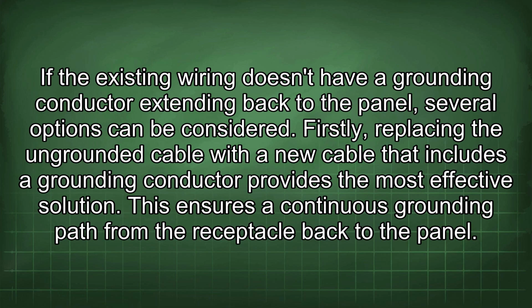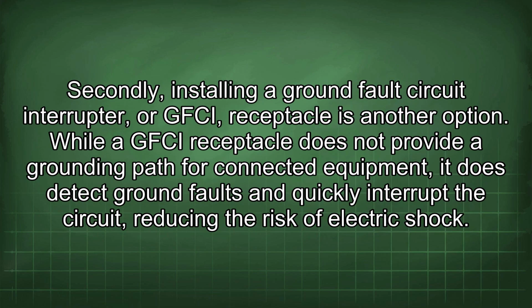Firstly, replacing the ungrounded cable with a new cable that includes a grounding conductor provides the most effective solution. This ensures a continuous grounding path from the receptacle back to the panel. Secondly, installing a ground fault circuit interrupter or GFCI receptacle is another option. While a GFCI receptacle does not provide a grounding path for connected equipment, it does detect ground faults and quickly interrupt the circuit, reducing the risk of electric shock.